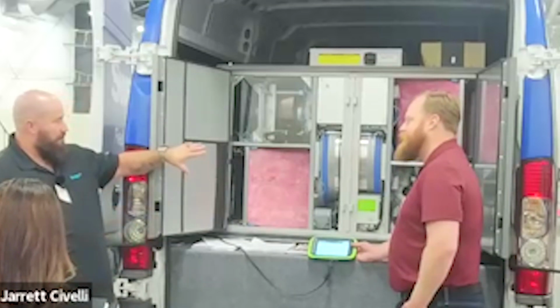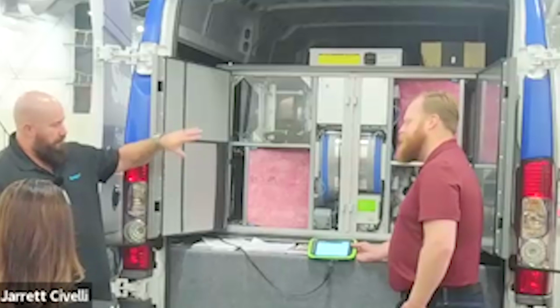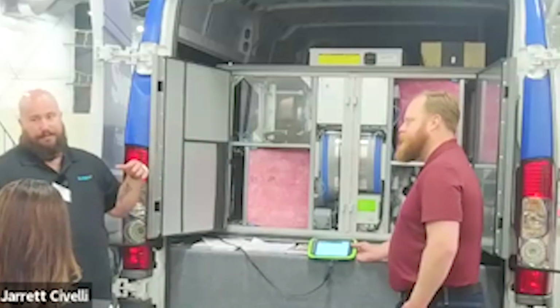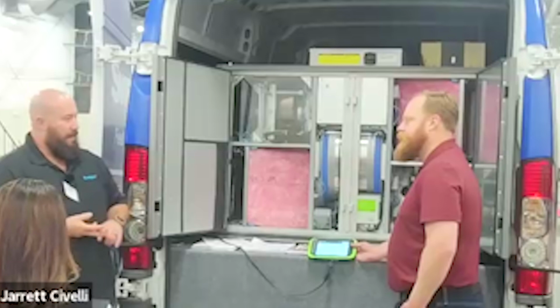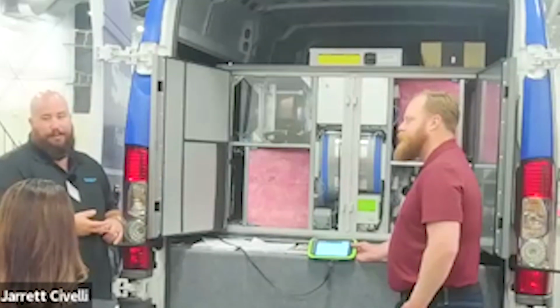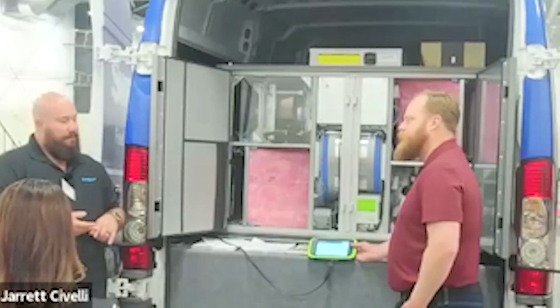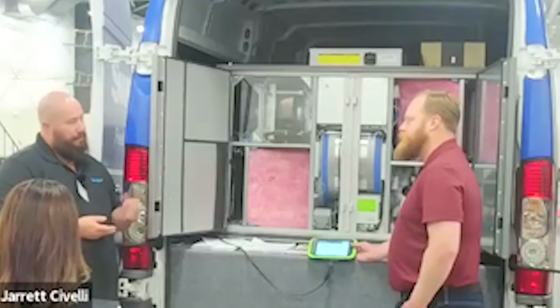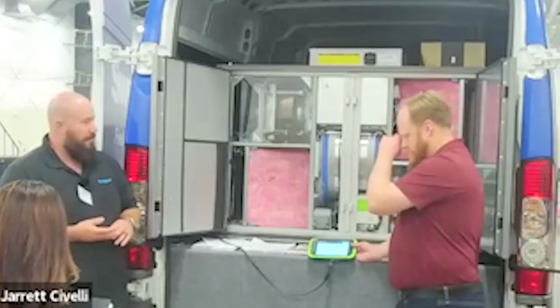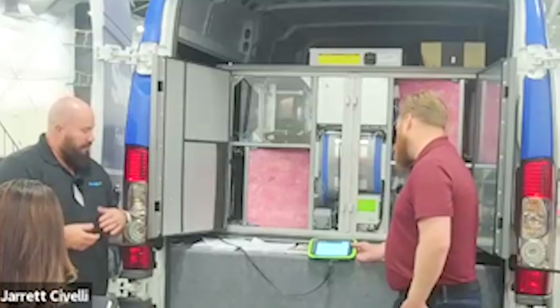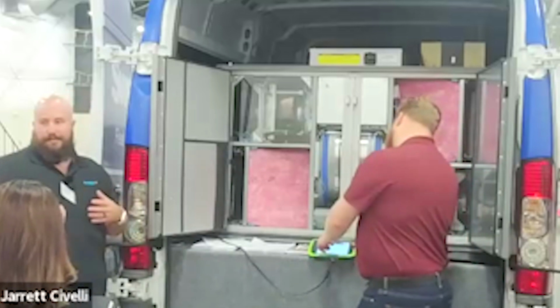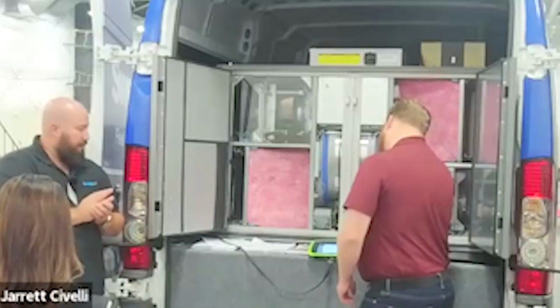Besides being able to control just the unit and what's built into it, there are expansion modules that take over boiler rooms. If you wanted to control the valves for post heat or post cooling, it'll take care of those on its own. If you had preheat, it'll take care of that too. You basically just plug in a couple different modules and some sensors.